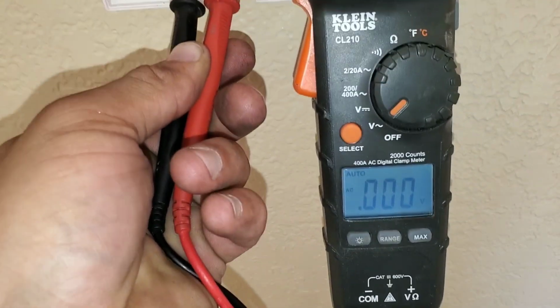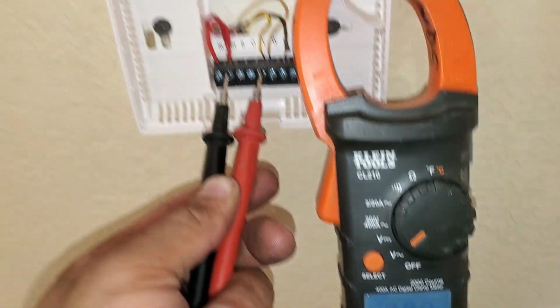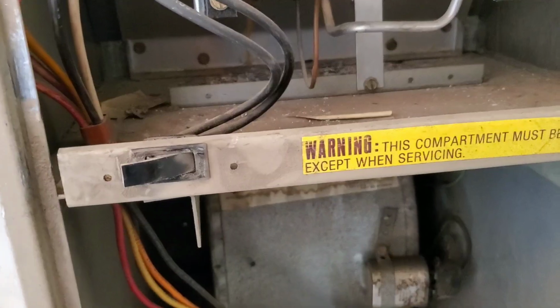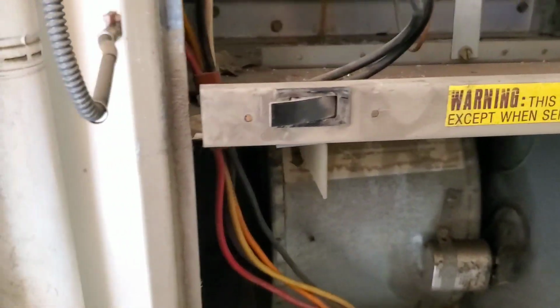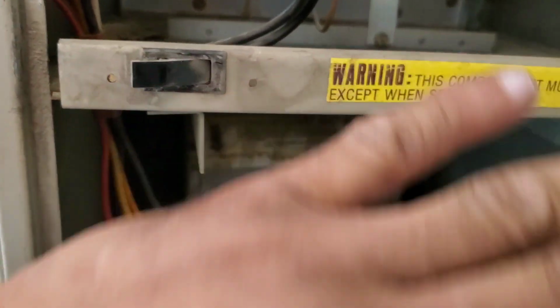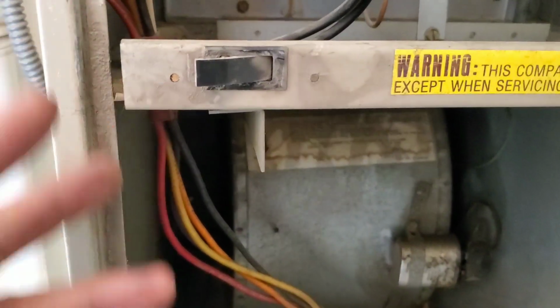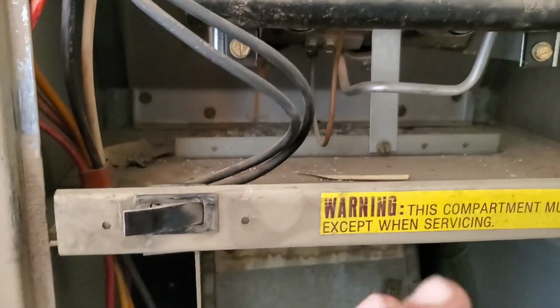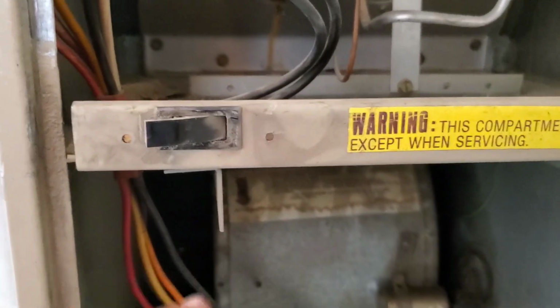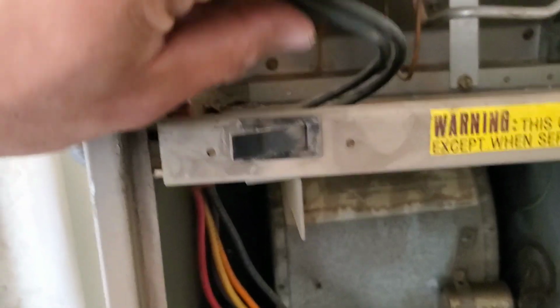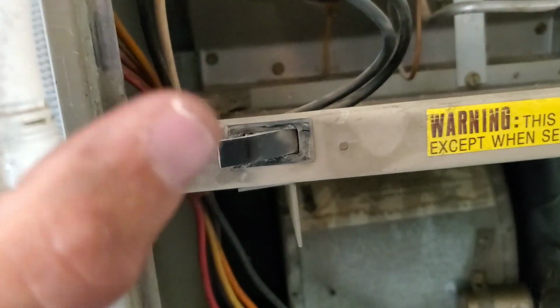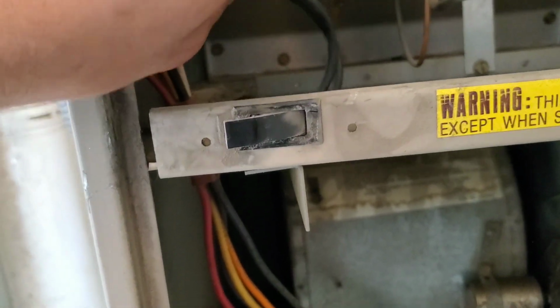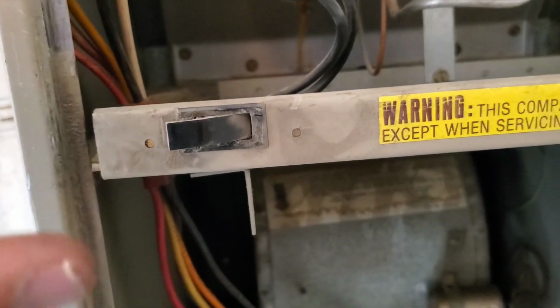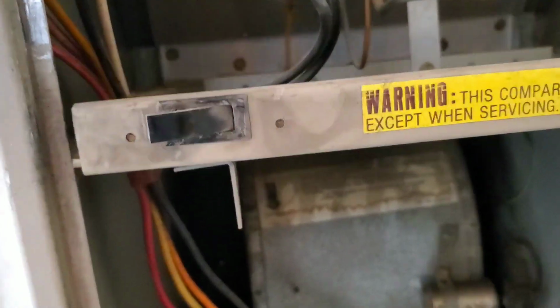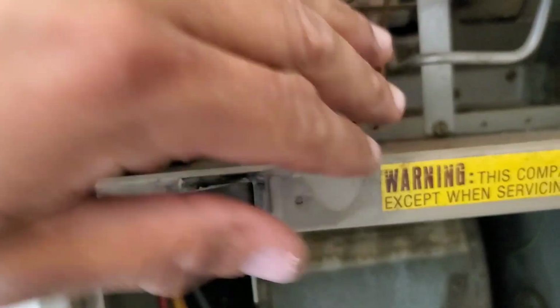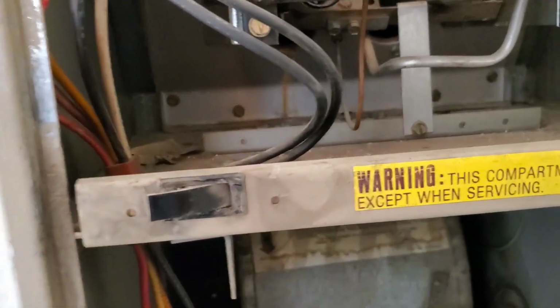So here you can see I have my multimeter set to volts AC, and I do not have voltage. The reason I don't have voltage is because my panel right now has been removed. The door switch acts as a safety so that when you're doing any repairs, it will immediately remove any power to your unit. A lot of times you see that guys will actually cut the wires and then they'll jump it. I caution against that, because what you're doing is you're eliminating your only source of safety. And when you bypass the switch, when you pull the panel, if you jump both wires, this unit will constantly have voltage on the system.